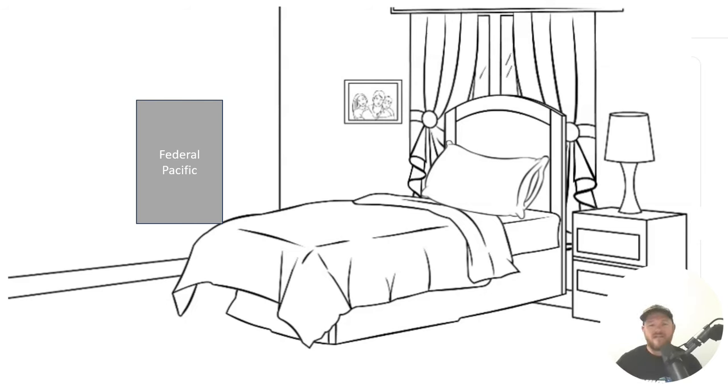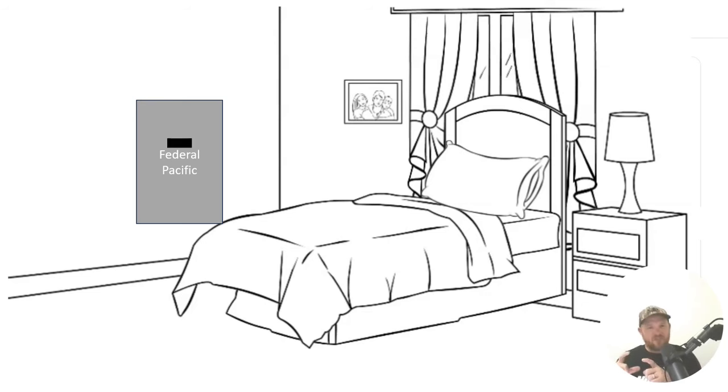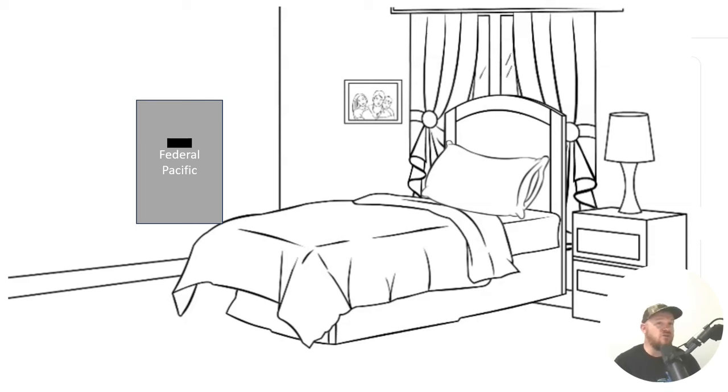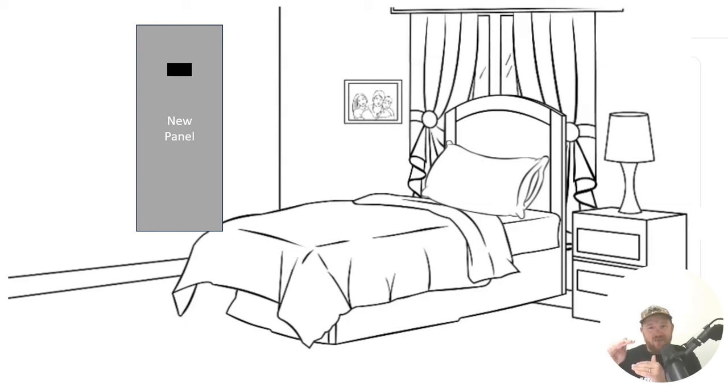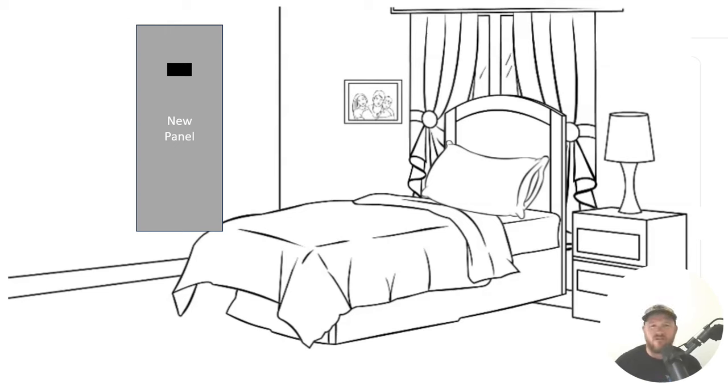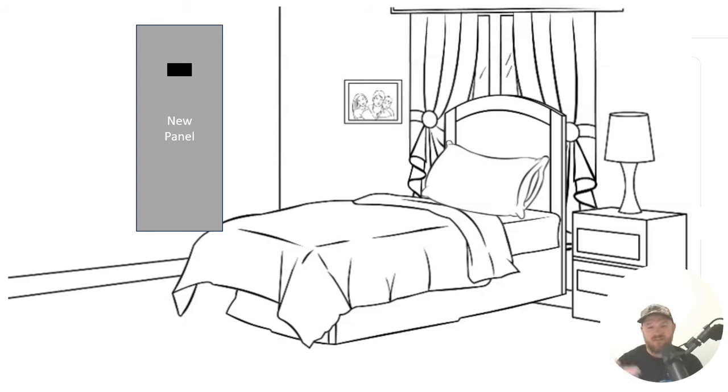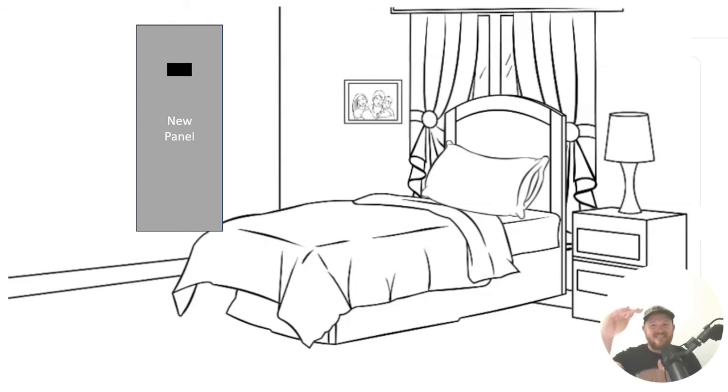Well, when you get there on that day, you see, hey, the main breaker here at this height, no big deal. It's a little bit smaller panel, and they've set it a little bit lower. Well, when you get your new panel, nice 40-circuit panel, you find out that it's a whole lot bigger, and that main breaker is going to be much higher than the previous main breaker. The question today is how high can that main breaker be located off the floor legally? Well, the correct answer is 6 foot 7, like we learned. So you're like, let's imagine in this situation that it's going to end up being 6 foot 9, this main breaker, because these new panels are so large. And your hole coming in the back is dictating kind of the height of that panel based off of the outside equipment. Happens all the time.